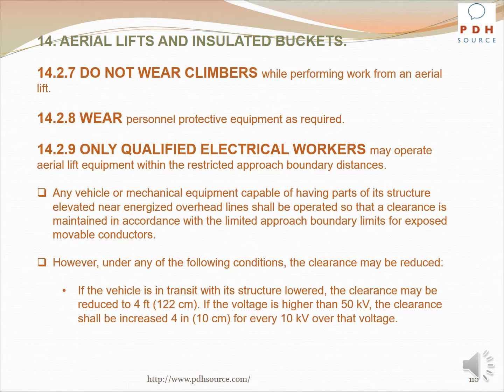Do not wear climbers while performing work from an aerial lift. Wear personal protective equipment as required. Only qualified electrical workers may operate aerial lift equipment within the restricted approach boundary distances. Any vehicle or mechanical equipment capable of having parts of its structure elevated near energized overhead lines shall be operated so that a clearance is maintained in accordance with the limited approach boundary limits for exposed movable conductors.